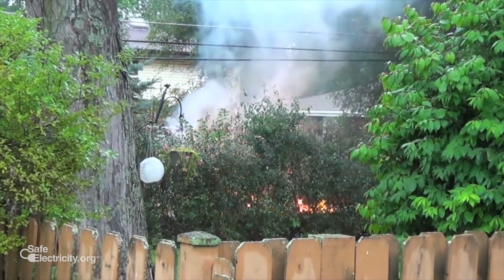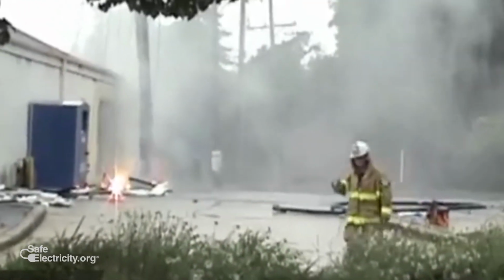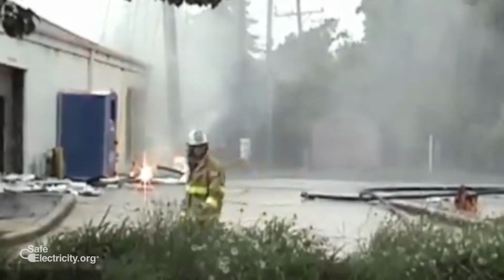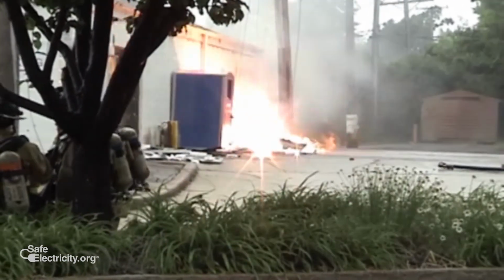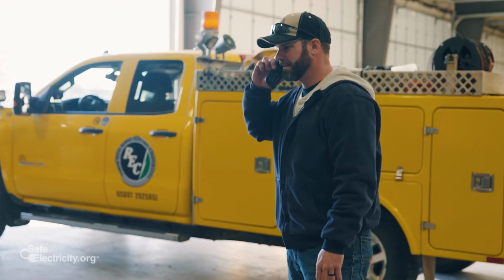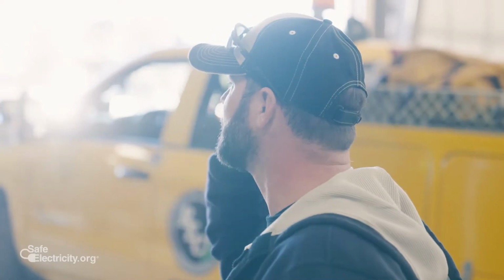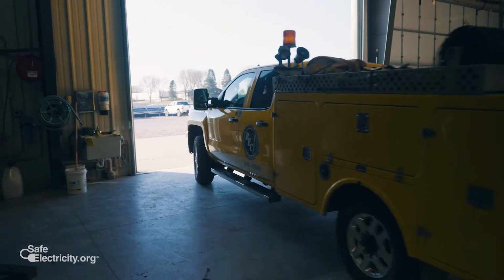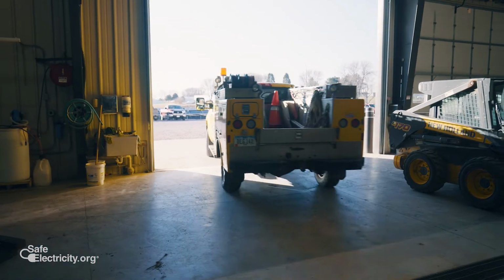If the transformer is on fire, they should leave it alone. Let the fire do its thing. Don't put water on it. Just let it burn itself out until the utility comes out. The main thing I can stress is call the utility company as quickly as possible. The sooner they're notified, the sooner they can get to the shop and head out to the area.